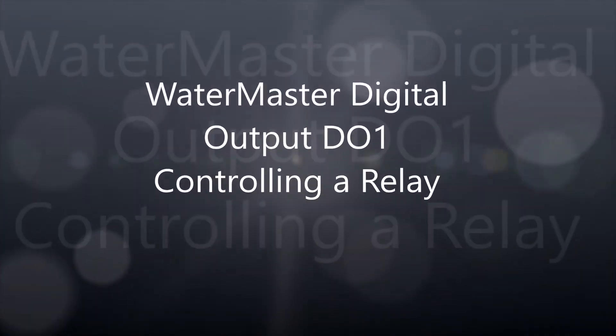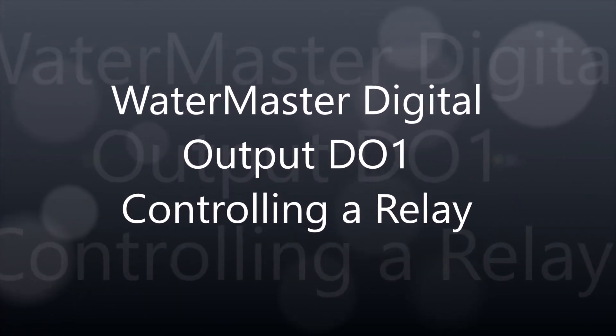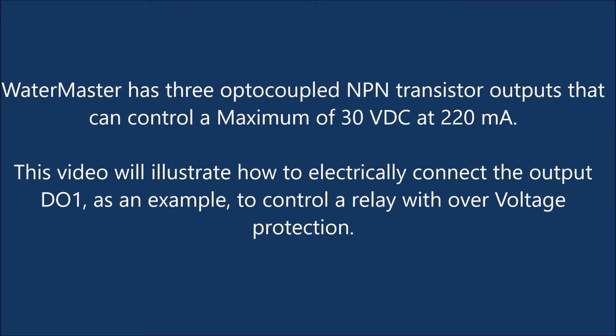Watermaster Digital Output DO1 controlling a relay. Watermaster has three optocoupled NPN transistor outputs that can control a maximum of 30 volts DC at 220 milliamps.